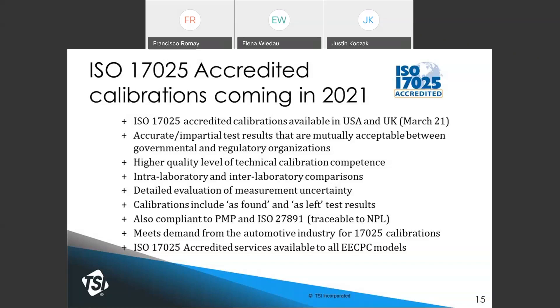For ISO 17025 accredited calibrations, a mandatory as-found calibration is performed before maintenance, followed by an as-left calibration after maintenance. In standard calibrations, the as-found is not done — maintenance is performed right away and only the as-left is reported. The calibration itself still follows the same procedure, is still PMP compliant, and still uses ISO 27891 as the standard.